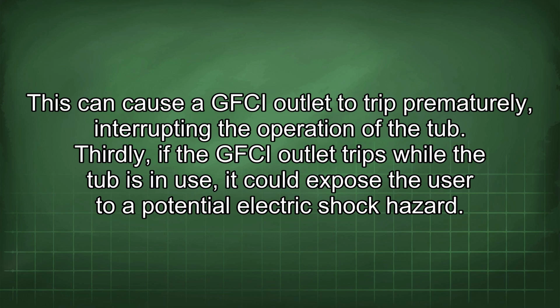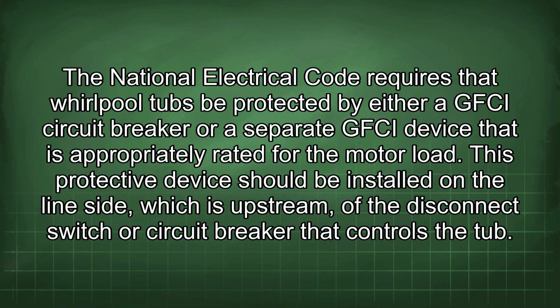Thirdly, if the GFCI outlet trips while the tub is in use, it could expose the user to a potential electric shock hazard. The National Electrical Code requires that Whirlpool tubs be protected by either a GFCI circuit breaker or a separate GFCI device that is appropriately rated for the motor load.